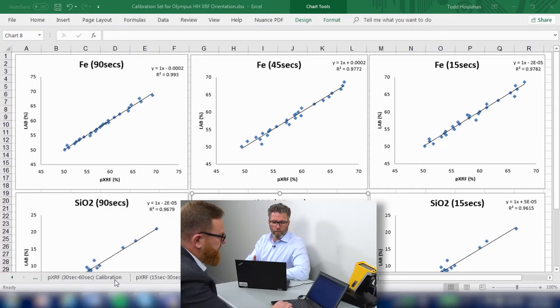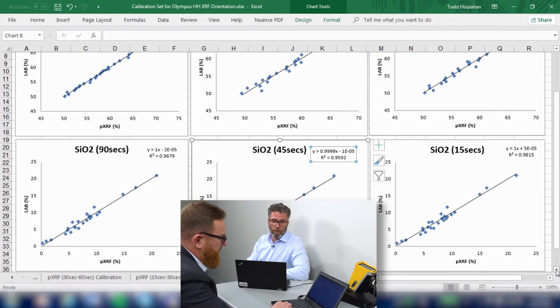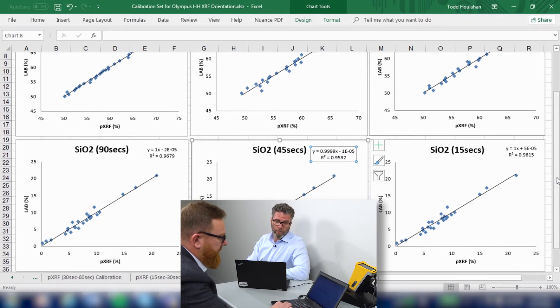Well Todd, interestingly enough, if we look at the comparison graphs, we have a heavy element and a light element. As we stated before, sometimes you need a longer testing time for particularly light elements, magnesium and silica.